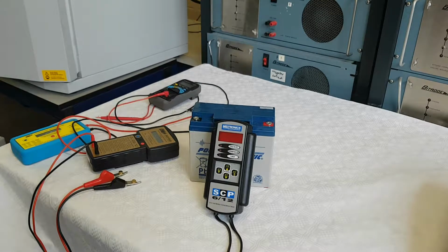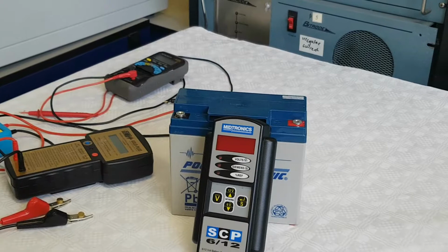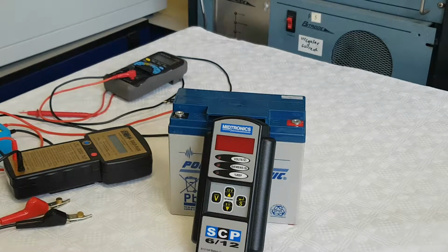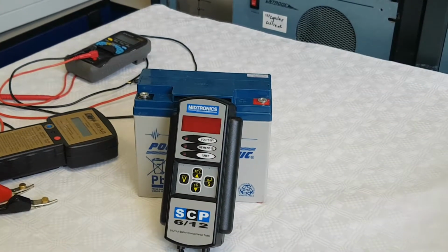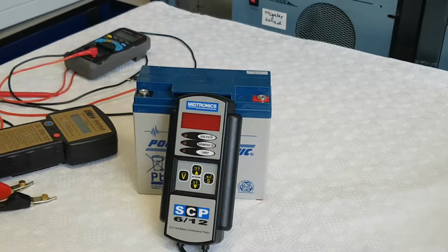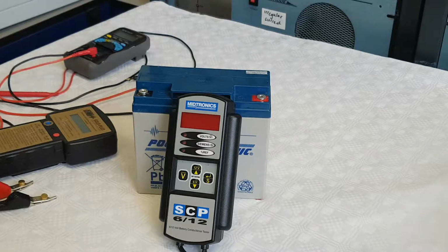There is an alternative tester on the market. It's called the Midtronics SCP 6/12. This tester measures conductance of a battery, and by inputting a reference conductance value of a good known battery, the tester will compare that value with the conductance of the battery under test. The result is then displayed as a percentage. So for a PS12 170, a 17 amp hour battery, the reference conductance value is 400. So by inputting that number, we can go ahead and test the battery.